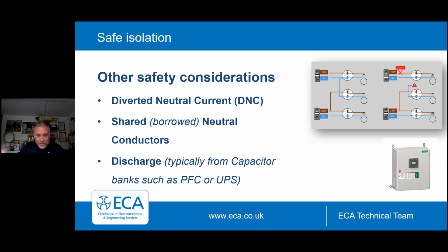Another great one, anyone who's worked in a 1960s home will understand the borrowed neutral from the lighting circuit for the hall stairs and landings. So many of us are familiar with sort of swapping out old domestic fuse box with modern boards with RCDs and RCBOs, only to discover that you can't get the lighting circuits to stay on because there's a shared or borrowed neutral. Okay. In this case, of a borrowed neutral, 2 circuits are supplied via a protected device on the load, and the circuit is connected often through the neutral. So you can get some back feed through that. So isolation of just the one circuit can therefore lead to dangerous situation where the circuit may prove dead, but it may be live or become live during work undertaken because of that second circuit and feedback through the neutral.